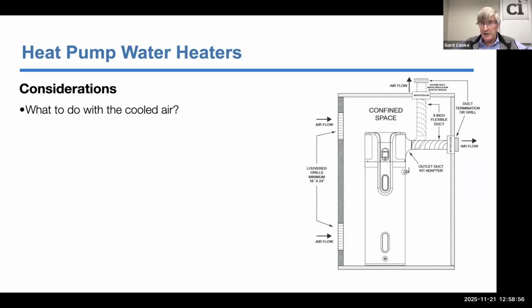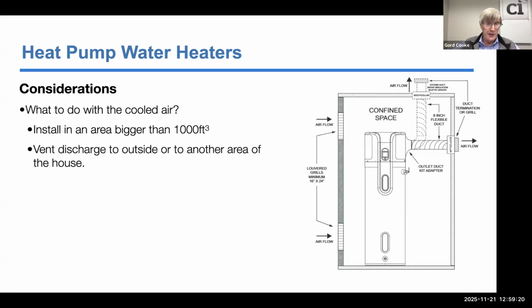There are some considerations: what do you do with that cooled air? You need a certain size room. If you have a basement, it's never an issue, but if it's slab on grade or a small multi-unit, you might have to find somewhere to dump that cold air. I don't normally recommend dumping it outside, normally into a floor joist system or something like that. As long as it's in an area bigger than 1,000 cubic feet, not square feet, and you can vent or discharge to another area of the house, you could decide to use electric heat only in the wintertime, so that's a good option.